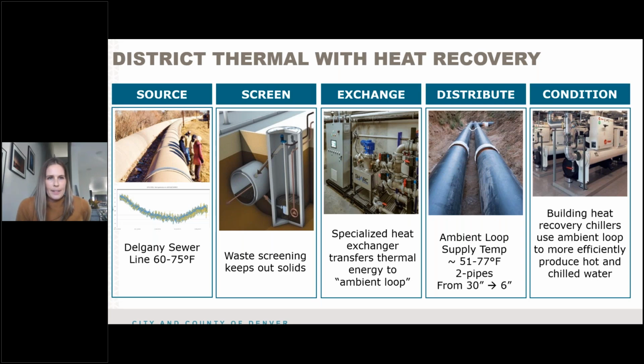And then the next, the box there on the screening. So we're going to pull that sewer into a wet well, screen out some of the bigger solids, and pump it up into the central plant. There, a special heat exchanger system further macerates the sewage and exchanges that thermal energy into a clean water condenser water loop. We usually call that our ambient loop. The ambient loop then sends water between 51 degrees and 77 degrees to our buildings via underground uninsulated HDPE piping.